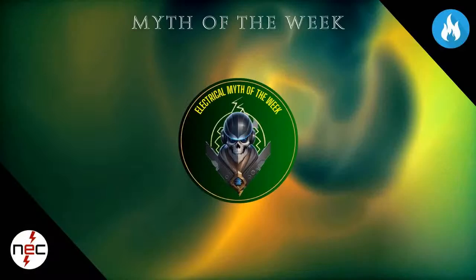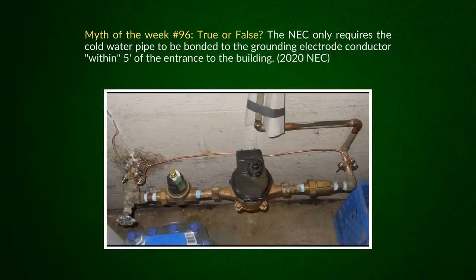Alright, so this is based on an actual true thing that happened. One of the job sites I was on, they thought that all they had to do was hit that point where the water enters the building. You can see that on the left, and per the code reference, the main water entry needs to be hit within 5 feet from where it enters the building. And then you can see there that they took the electrode conductor across and jumpered that meter and backflow preventer.